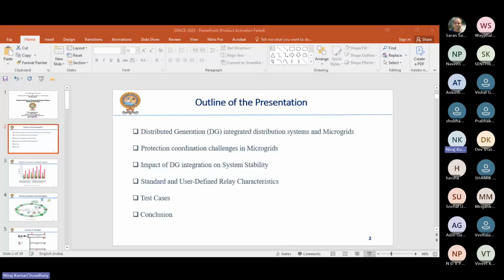And after that, I will showcase one of the examples where I have considered a 7 bus microgrid system, and how the protection coordination problem has been formulated in that test bed system, and how the optimal settings of the relays along with the total operation time of the different relays are calculated with the help of a few optimization techniques that we will see.